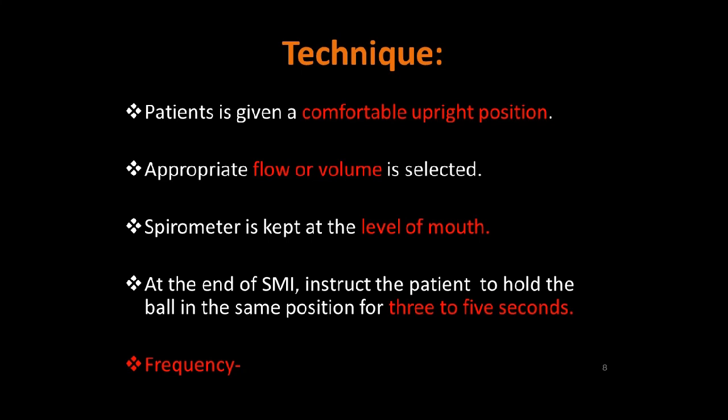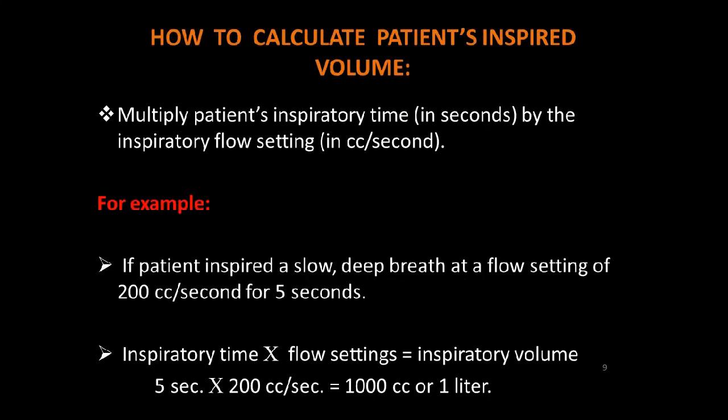To calculate the patient's inspired volume, multiply the patient's inspiratory time in seconds by the inspiratory flow setting in cc per second. For example, if the patient inspires a slow deep breath at a flow setting of 200 cc per second for 5 seconds, then: 5 seconds × 200 cc/second = 1000 cc, or one liter.